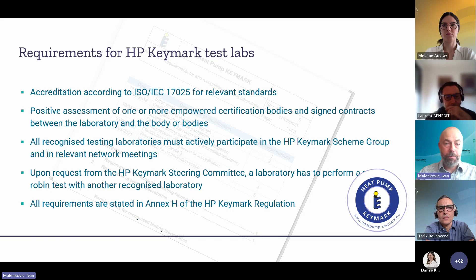So what does it really mean to be accredited according to ISO 17025? ISO 17025 gives you the general requirements for the competence of testing and calibration laboratories. What you have to have is an implemented and well-documented quality management system with clear processes which follow the relevant standards you have been accredited for. You also have to show traceable changes. That means if something in your processes changes, or something in the standard or in a testing procedure changes, you have to have it in your documentation, so that you can trace back results, for example from a test you have done maybe 10 years ago. After 10 years, you still have to be able to trace back what you were doing at that time.